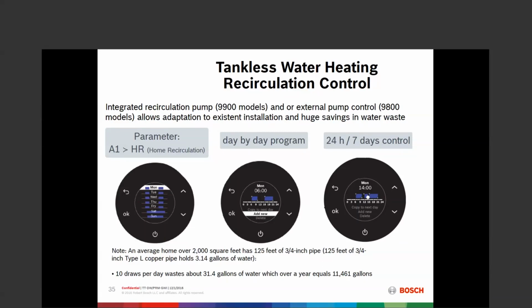Then for every 15 minutes until 9:30, it's going to bring that circulator on and run that test again, and run that circulator until the water comes back within 10 degrees of set point. That is adjustable to as low as 5 degrees or as much as 20 degrees. That is adjustable for different levels of comfort, so we can do that.